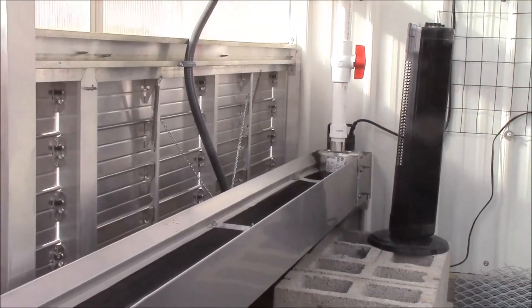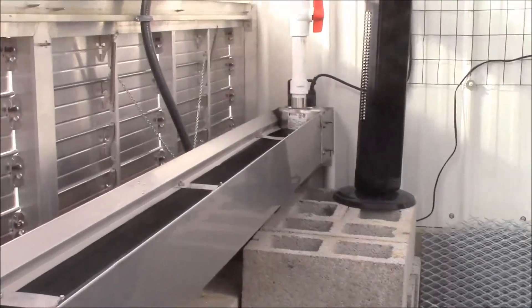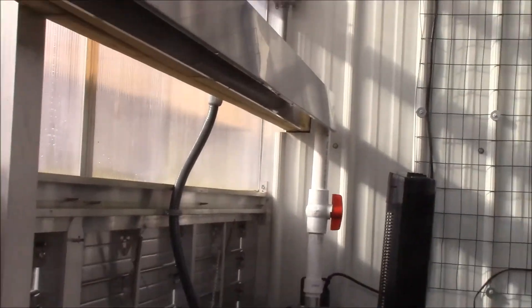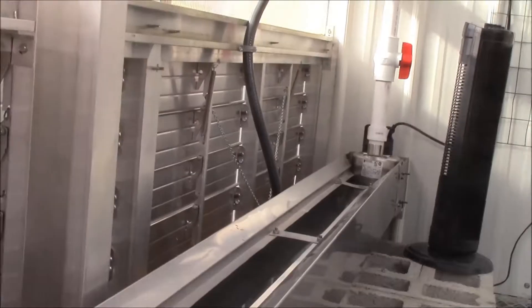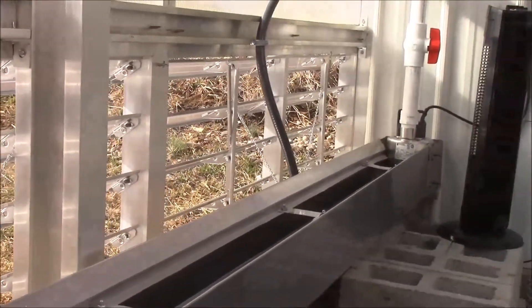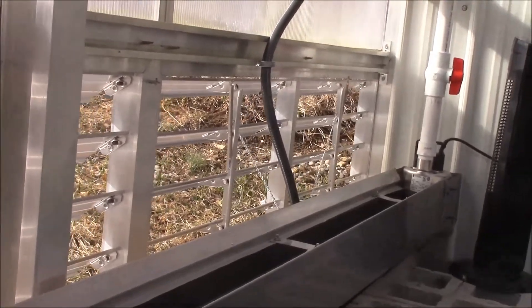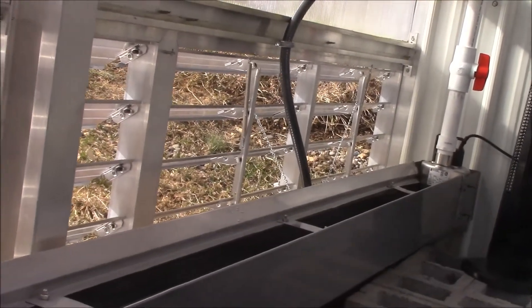Down at the end of that trough is the pump — the pump will be pumping water up into the top. There is a two-inch pipe with holes in it, and there are pads that go across here. It pumps water down the pads and the fans will pull air in through these. They're opening right now as you can see, and now the fan's going to go on. It takes care of temperatures just absolutely perfectly.